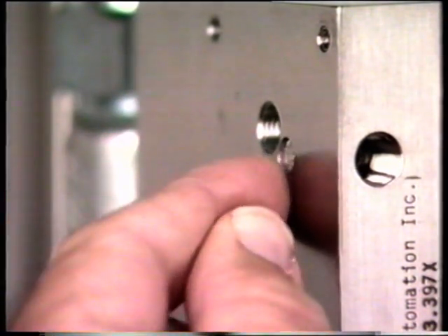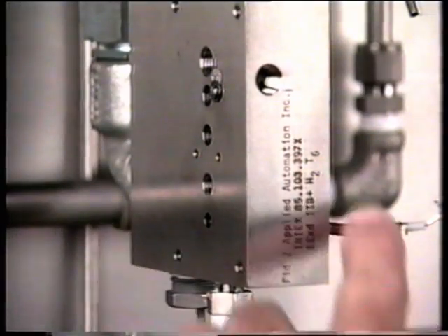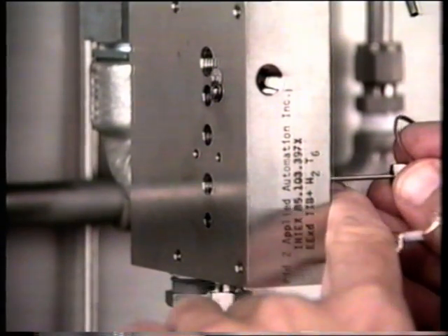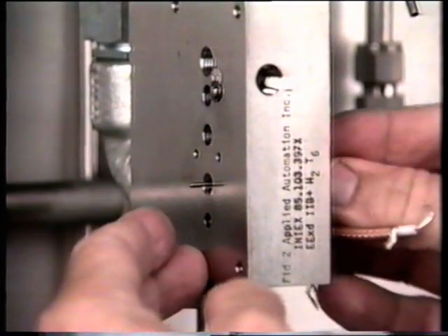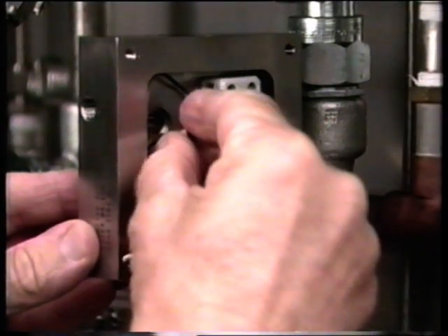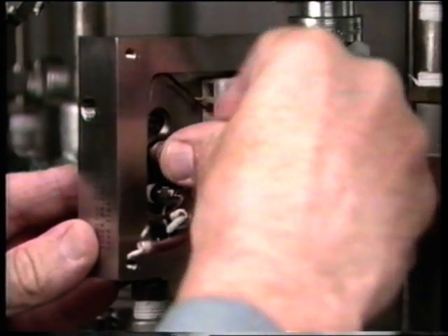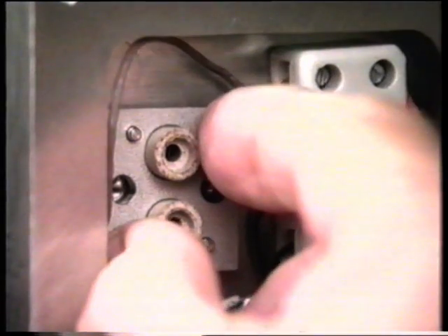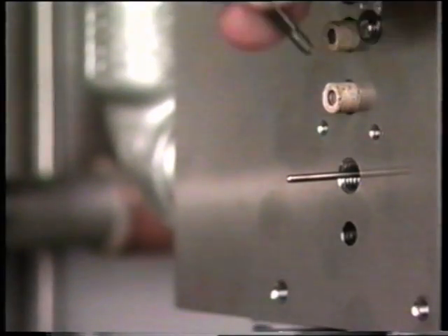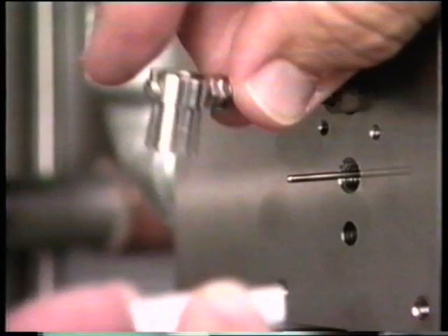Begin by replacing the air filter disc. Insert the thermocouple through its fittings and fasten it in place, and connect the wiring. Install insulator O-rings in the bias ignite and collector cavities. Insert the bias ignite and collector insulators through the cavities containing the O-rings and press them into place. Place the insulator clamp plate over the two insulators and clamp it evenly in place with the bias ignite and collector ground clamps. Insert the collector electrode into its insulator.